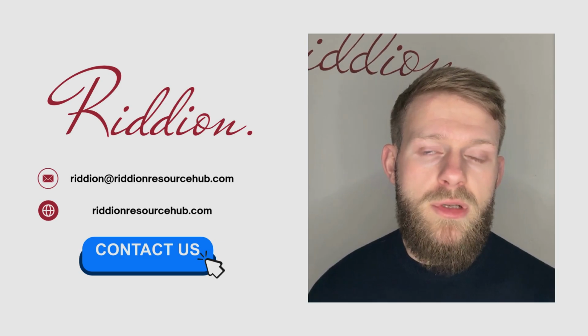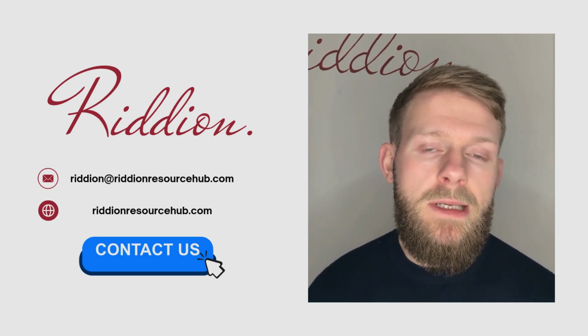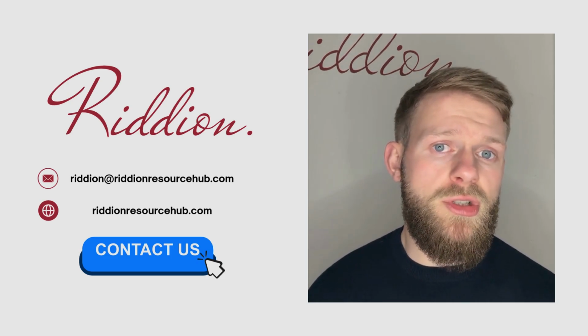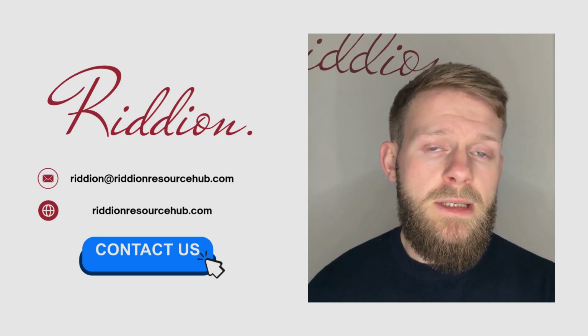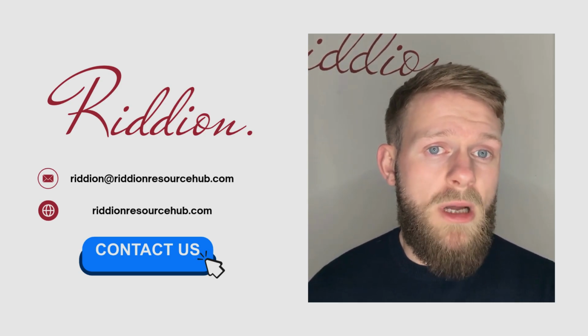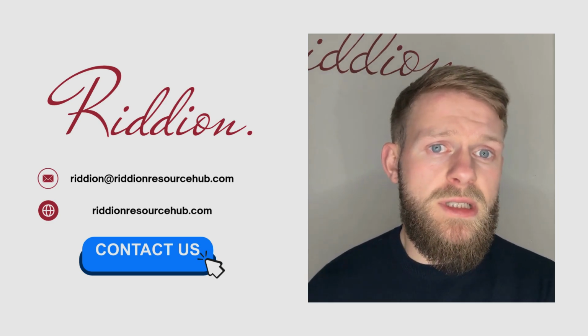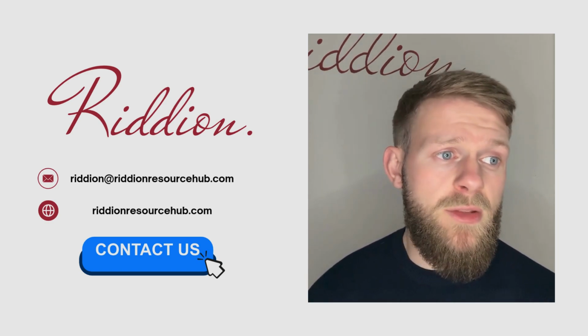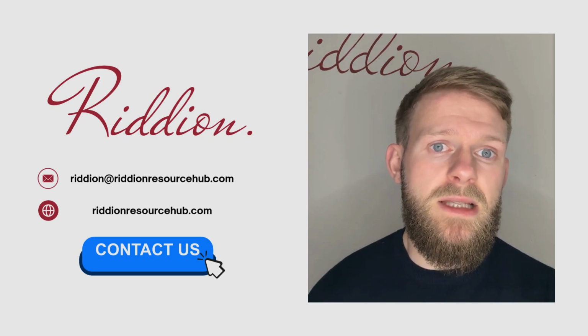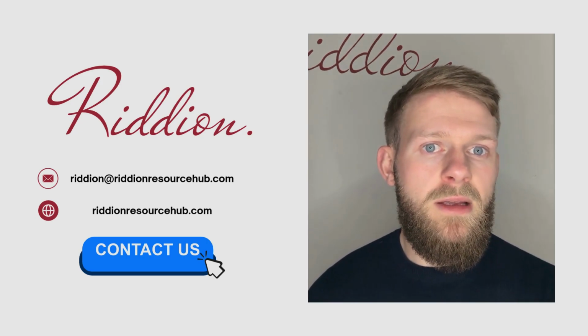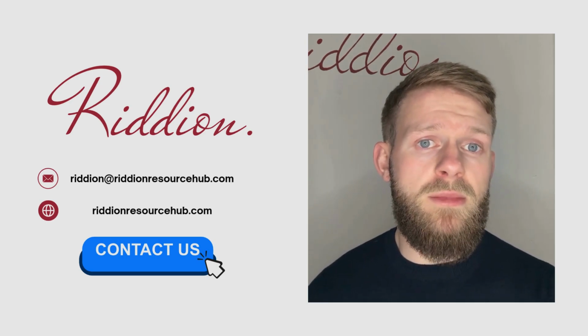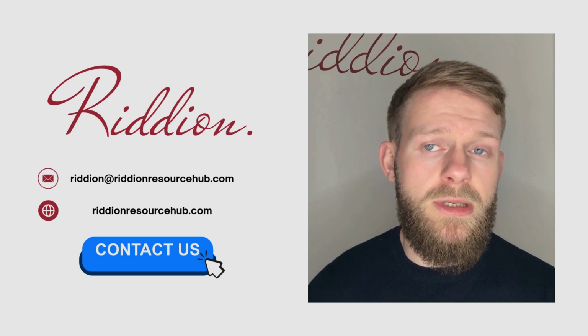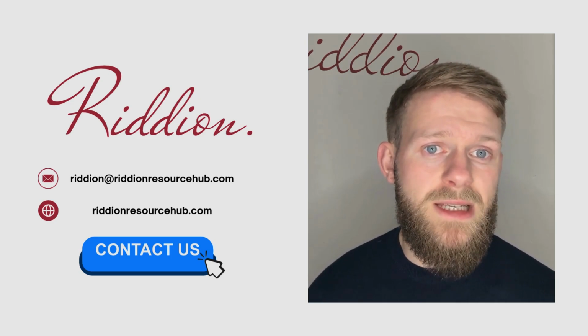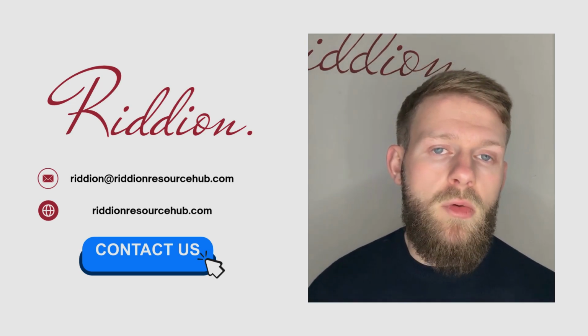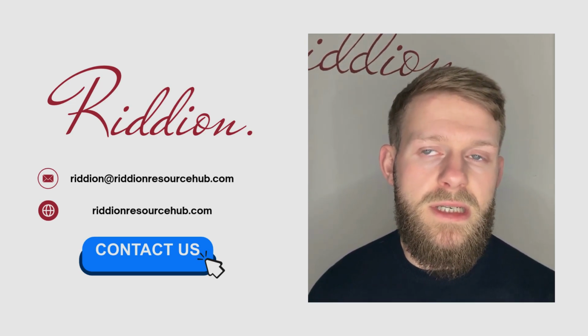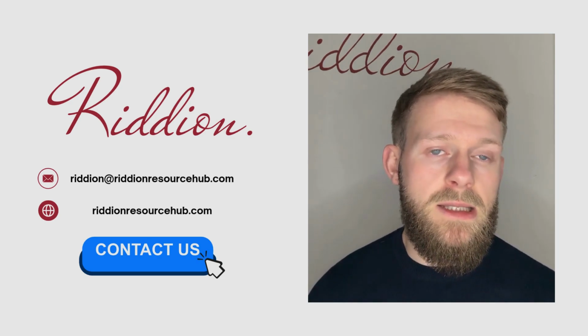Finally, if we talk about cost and service fees, notified bodies set their own pricing structures, which means fees can vary significantly. These fees cover application review, audits, and ongoing surveillance, and they add up over time. But the key to this is that cheaper isn't always better. The cheapest option might also mean longer review times. It might mean inconsistent communication or a frustrating certification experience. So instead, look for a notified body that balances efficiency with transparency and long-term support.